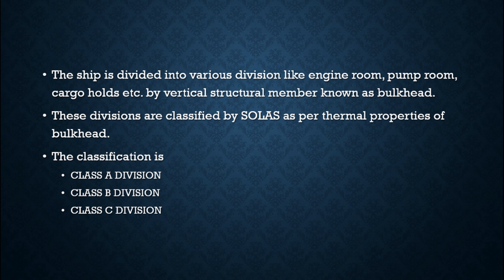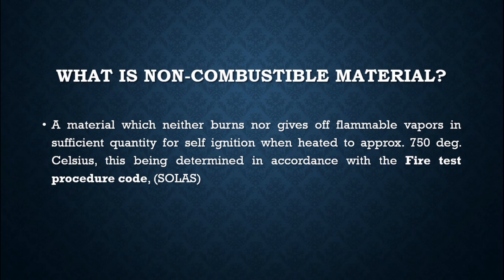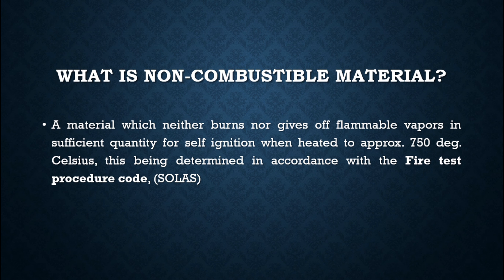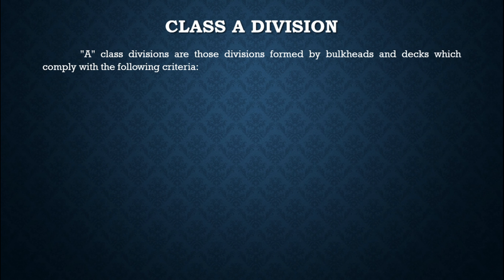Before discussing the divisions, we will see what is a non-combustible material. A non-combustible material is one which neither burns nor produces flammable vapors in sufficient quantity for self-ignition when heated to approximately 750 degrees Celsius. This is determined in accordance with the fire test procedure code mentioned in SOLAS.